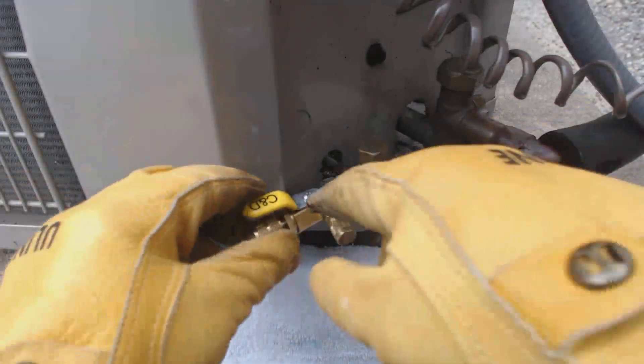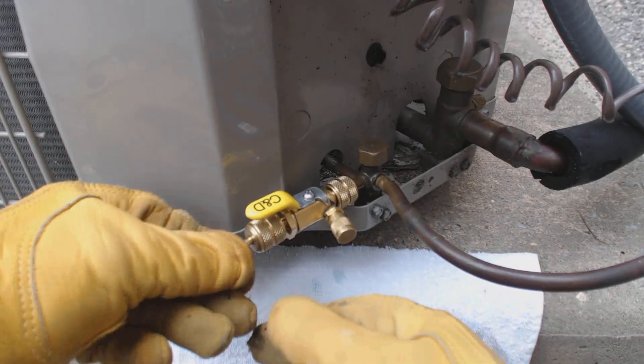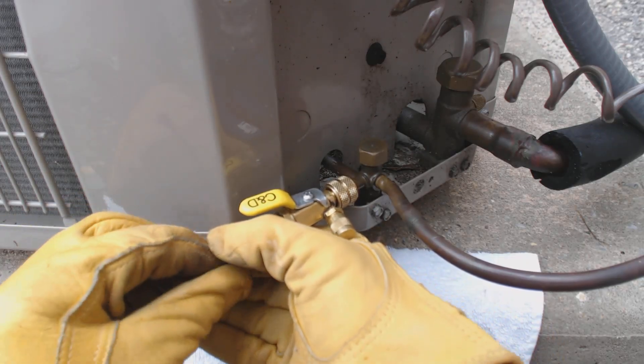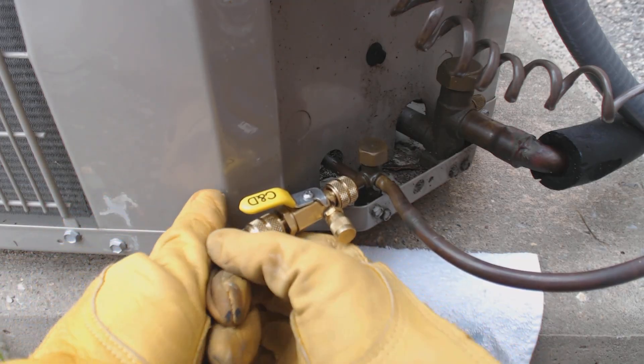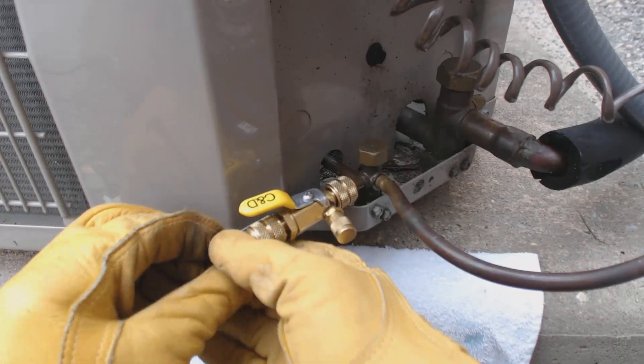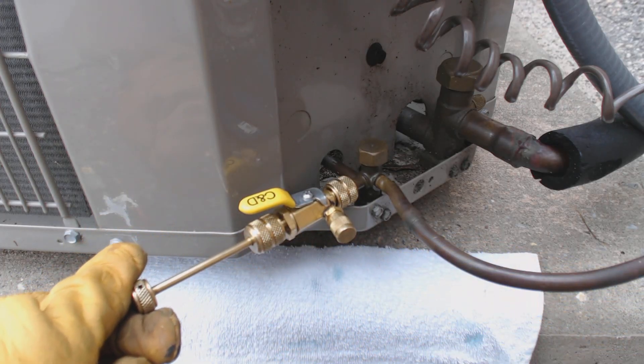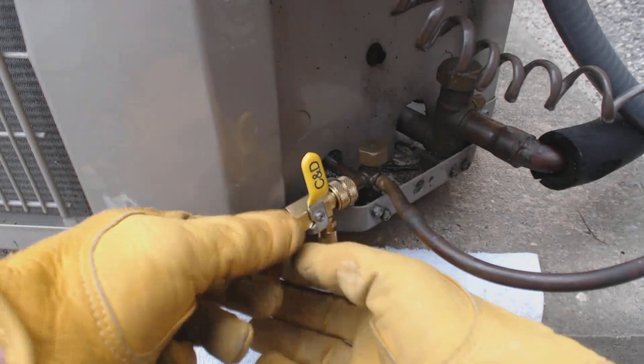All the rest of the caps are tight. The pressure is automatically going to want to push this back. What you're going to want to do is take this knob, push it forward, and unscrew the Schrader valve. It feels like we have it now, so we'll pull this back, turn it, shut the valve, and disconnect this.